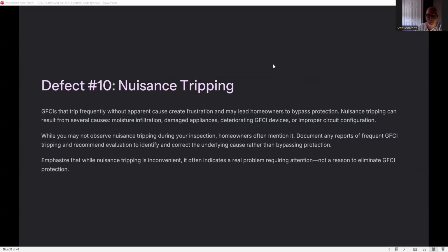Nuisance tripping. GFCIs that trip frequently without cause create frustration and may lead homeowners to bypass protection. Nuisance tripping can result from several causes, as we talked about: moisture infiltration, damaged appliances, deteriorating GFCI devices, or improper circuit configuration. While you may not observe nuisance tripping during the inspection, homeowners often mention it.